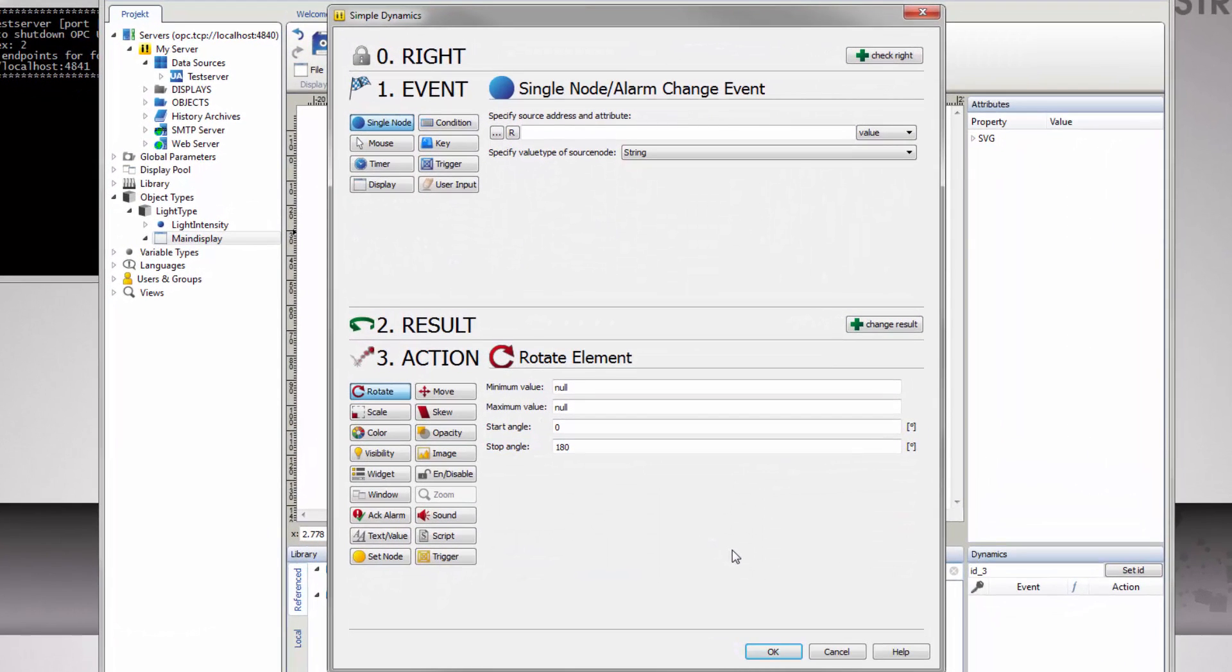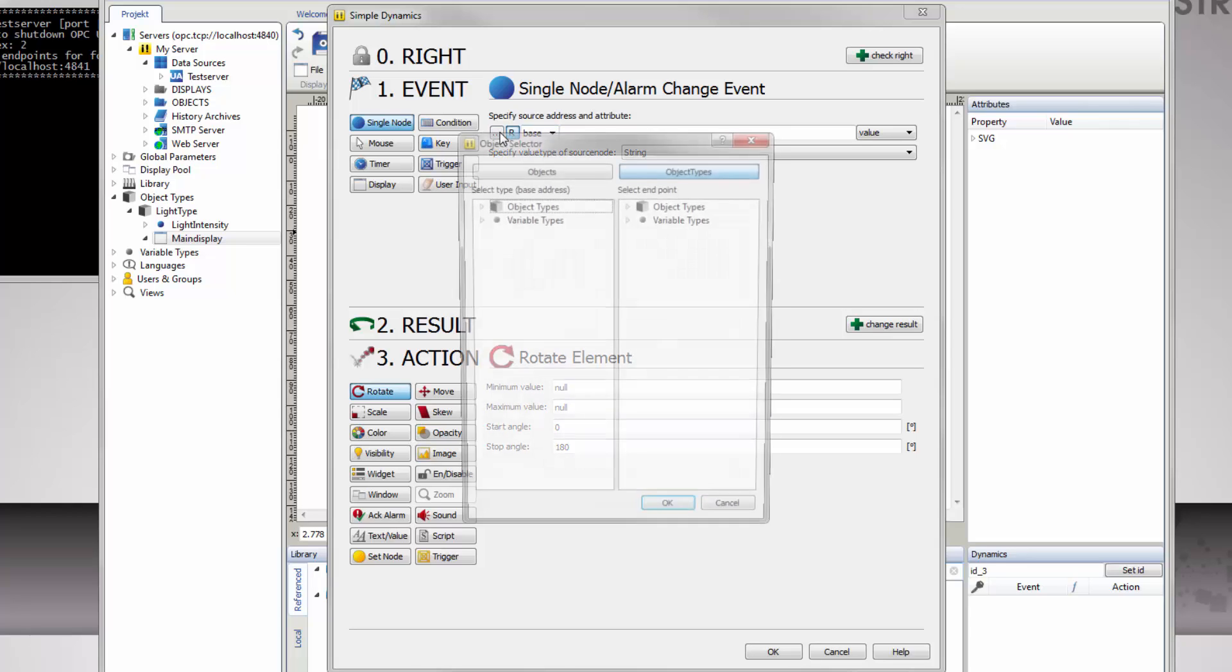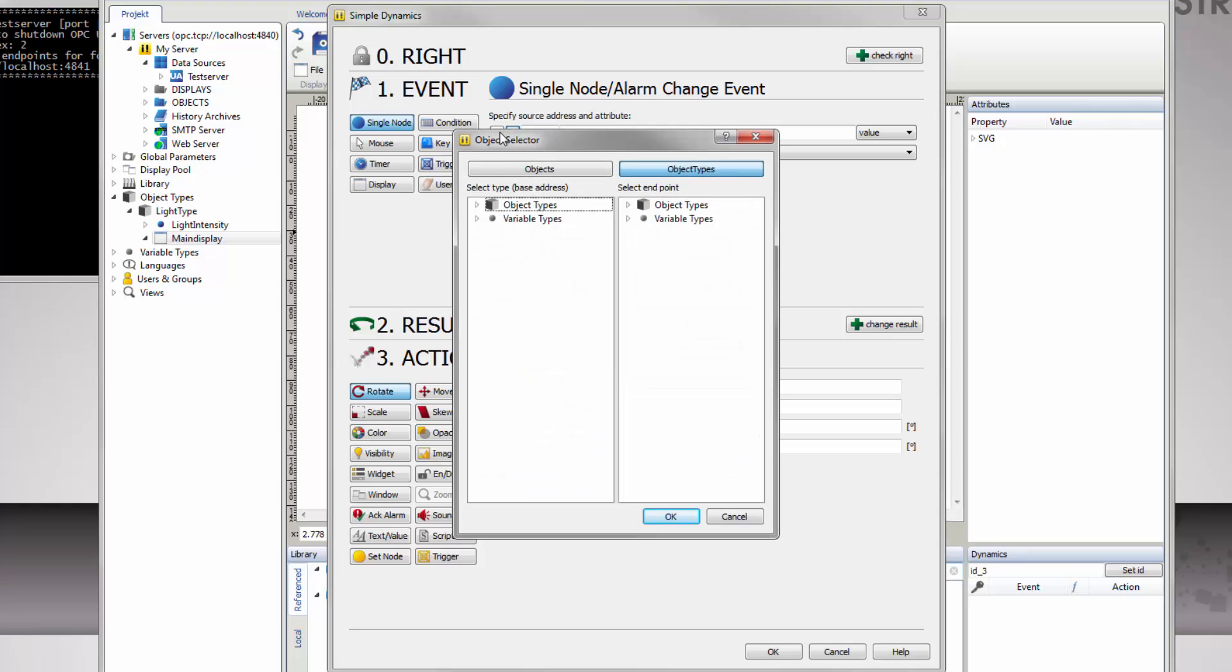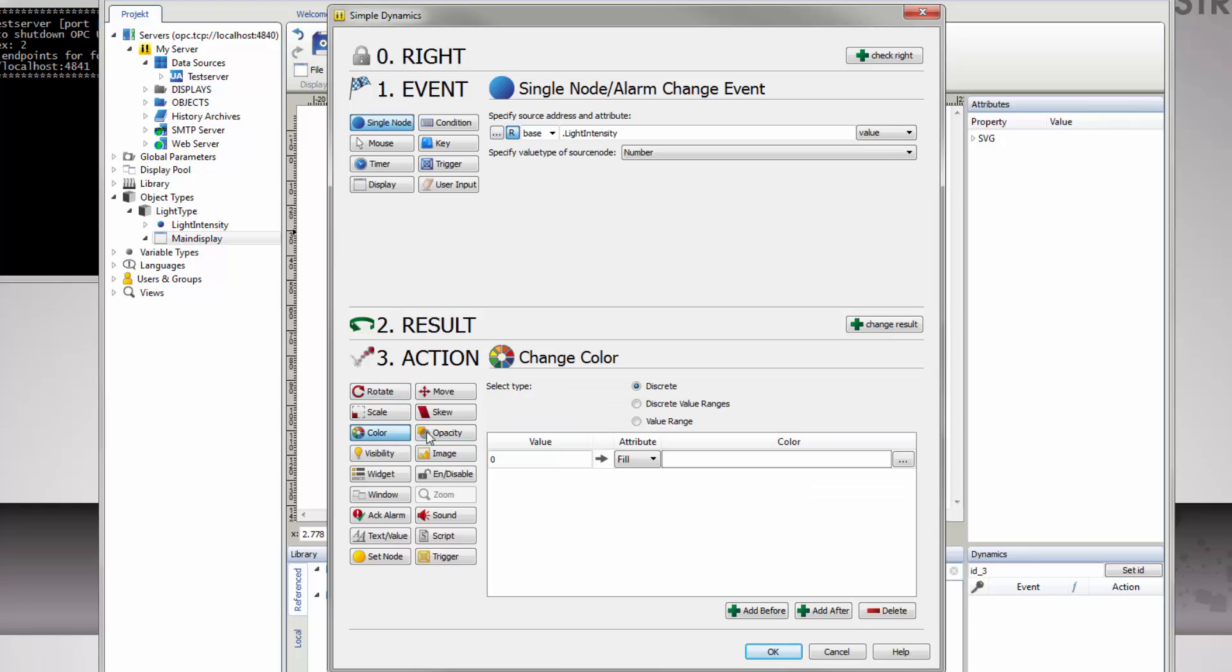To display the current light intensity, create a new dynamization by right-clicking the circle and select add simple dynamic. The pre-selection node for the event is correct. Activate relative addressing here as well by clicking the R button. Base must be selected in the drop down list. Then open the dialog for addressing with a click on the button with the three dots on it. In the left column, select light type as base address, and in the right one, light intensity as endpoint. Save your selection with OK.